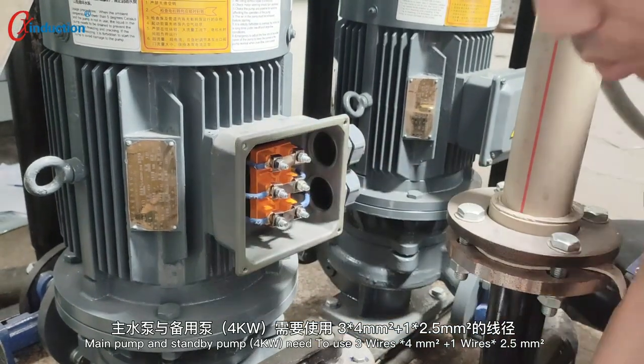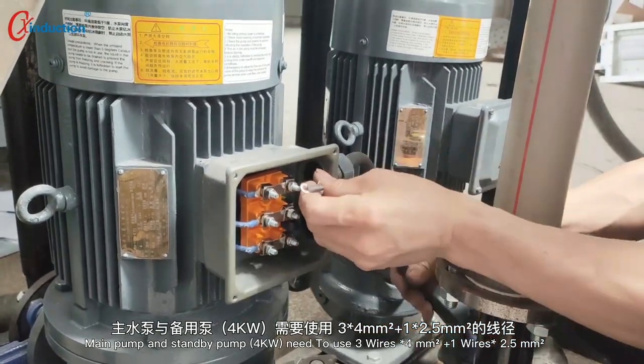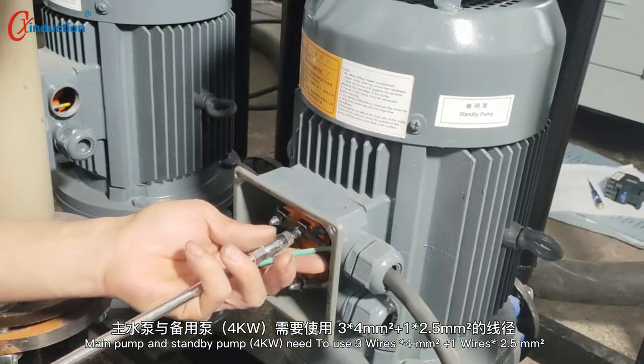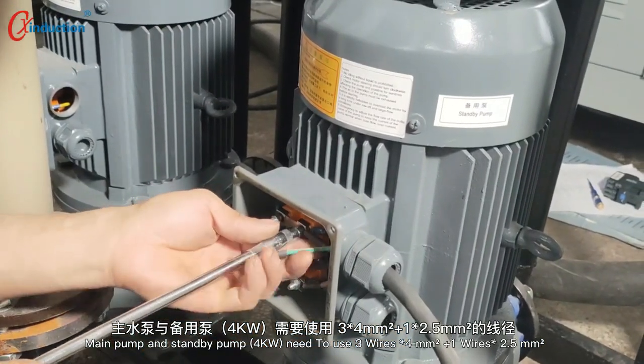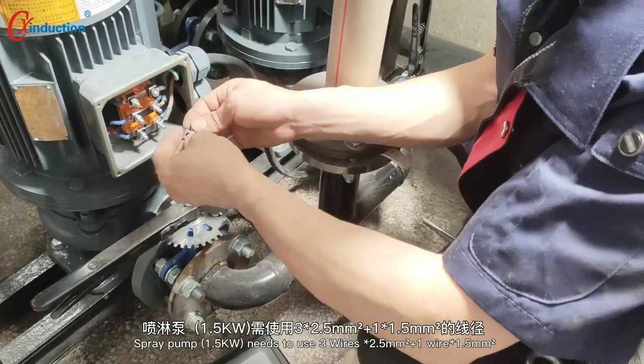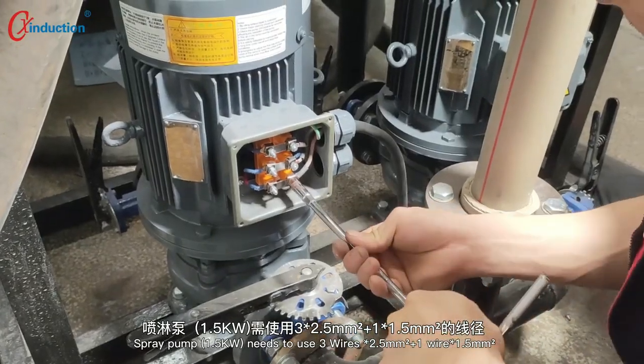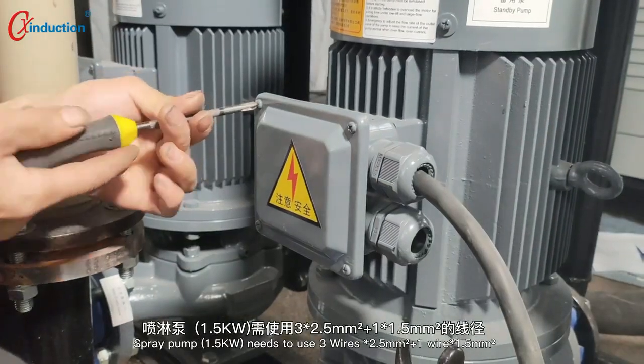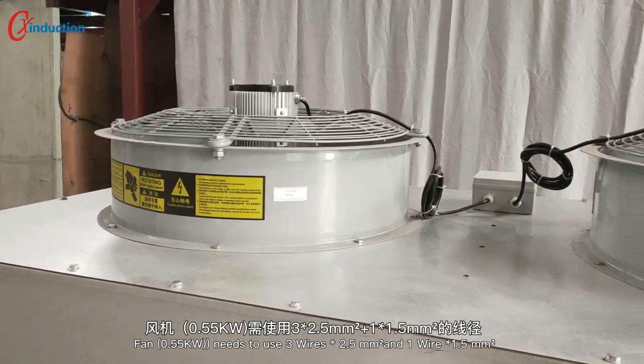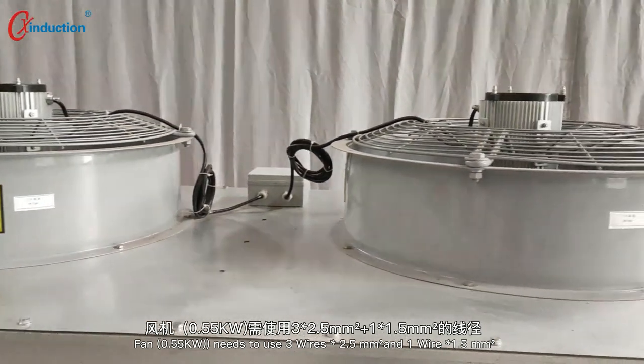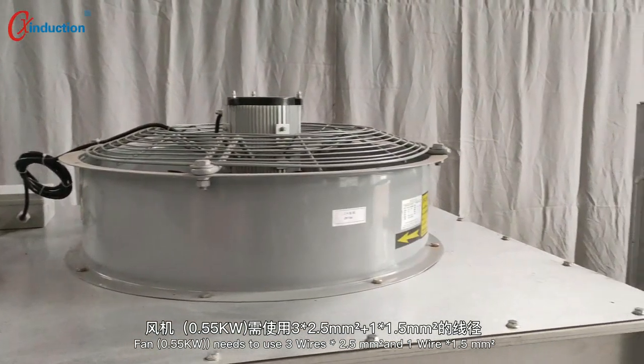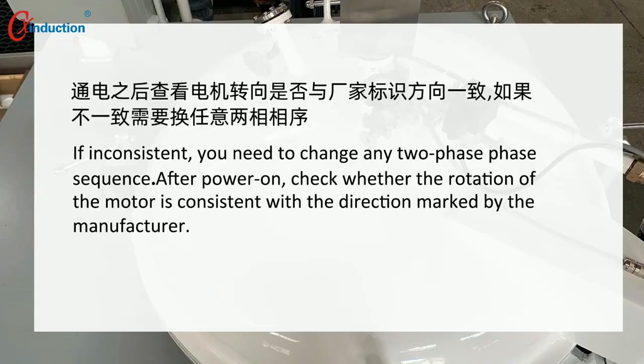Main water pump and standby pump 4 kW need to use 3 wires with 4 square millimeter and 1 wire with 2.5 square millimeter. Spray pump 1.5 kW needs to use 3 wires with 2.5 square millimeter and 1 wire with 1.5 square millimeter. Fan 0.55 kW needs to use 3 wires with 2.5 square millimeter and 1 wire with 1.5 square millimeter. After power on, check whether the rotation of the motor is consistent with the direction marked by the manufacturer. If inconsistent, you need to change any two-phase sequence.